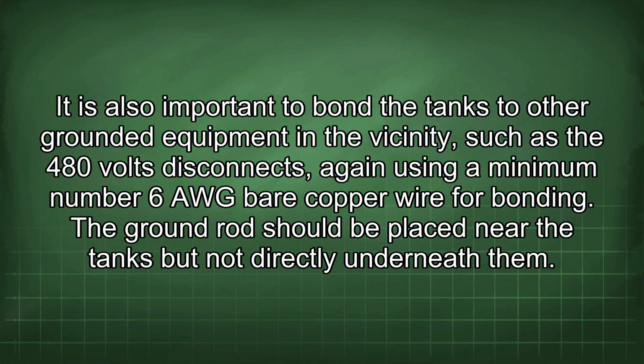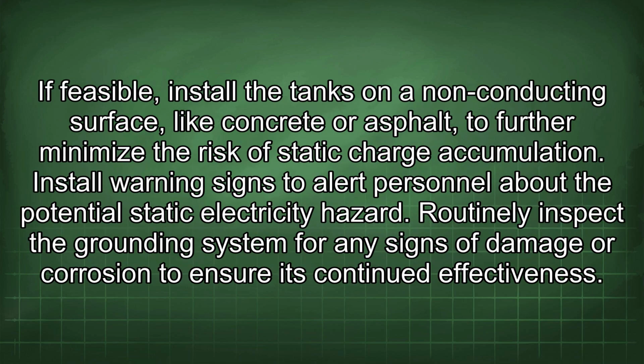wire. It is also important to bond the tanks to other grounded equipment in the vicinity, such as the 480 volts disconnects, again using a minimum number 6 AWG bare copper wire for bonding. The ground rod should be placed near the tanks but not directly underneath them. If feasible, install the tanks on a non-conducting surface, like concrete or asphalt, to further minimize the risk of static charge accumulation. Install warning signs to alert personnel about the potential static electricity hazard.